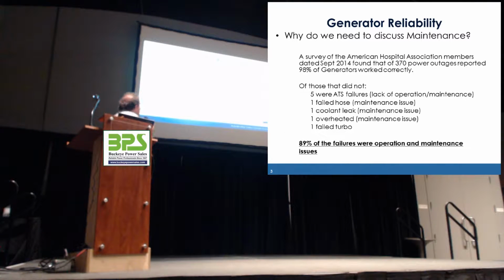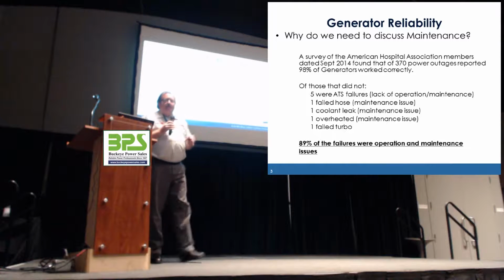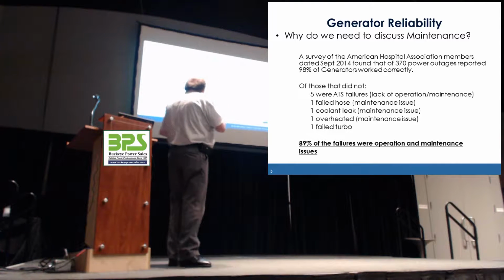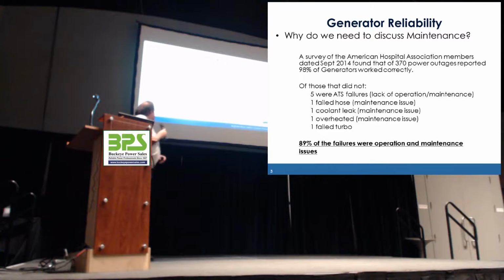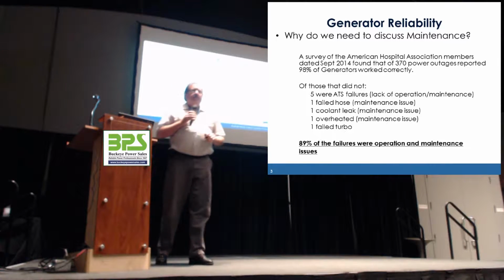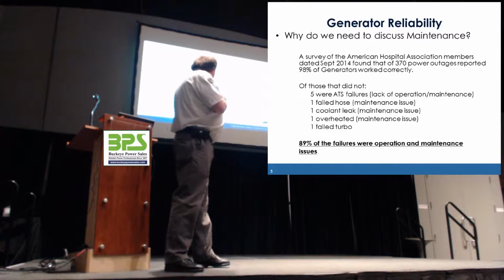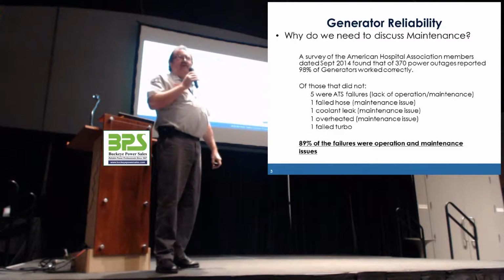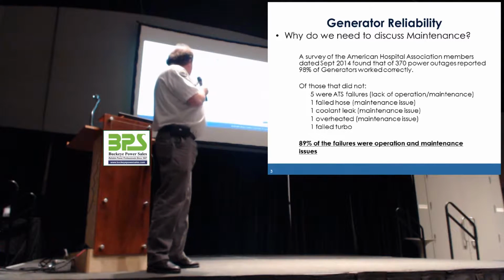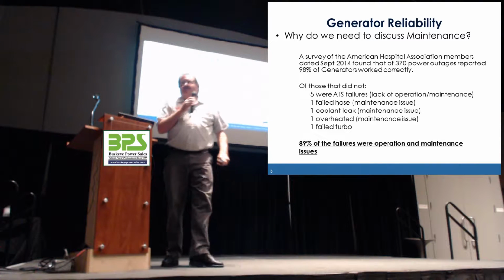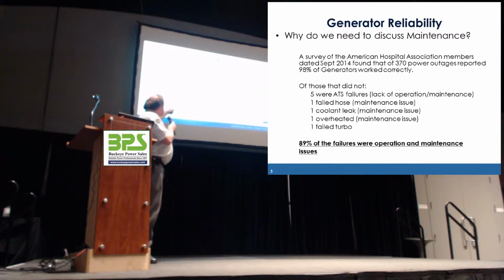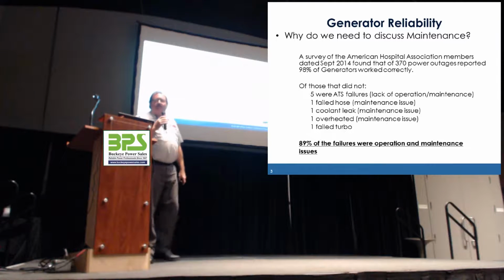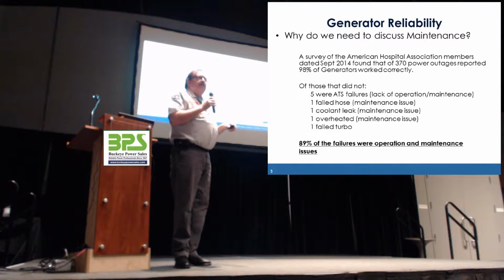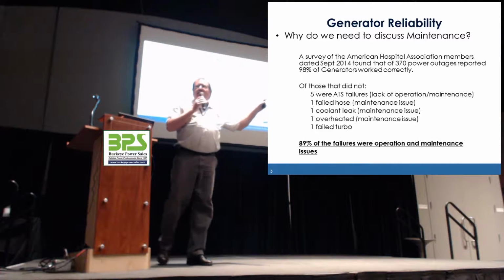So why do we care about maintenance? Why do we care about generator maintenance? Well, the American Hospital Association did a survey here real recently of 370 power outages. 98% of them worked fine. The 2% that didn't, there were 5 with transfer switch failures. There was a failed hose, a coolant leak, 1 overheated, 1 failed turbo. So all of those items on there, all of them except maybe the failed turbo, can be attributed to lack of operation and lack of maintenance.